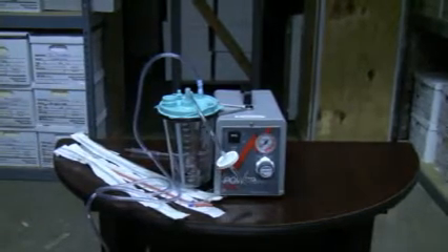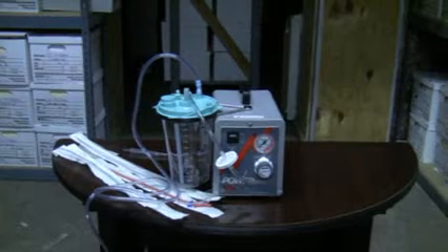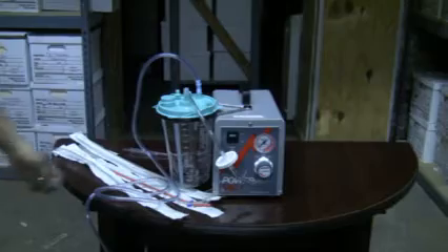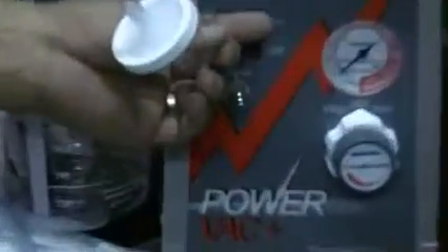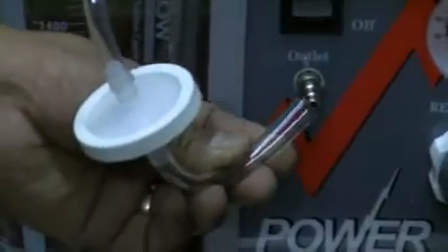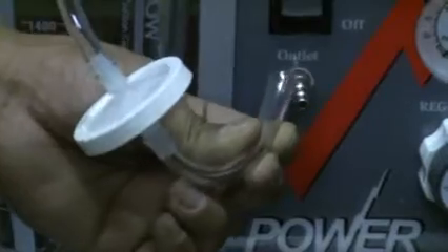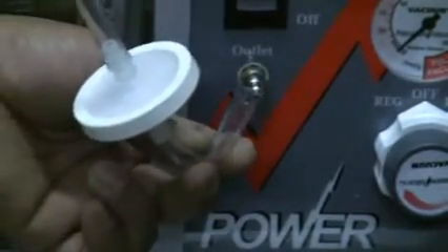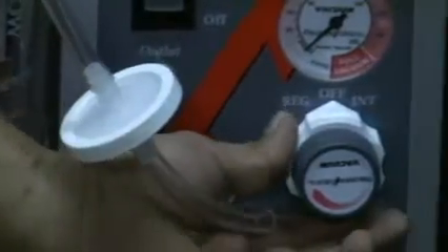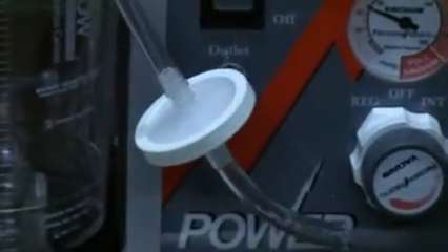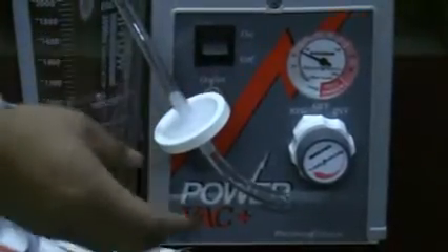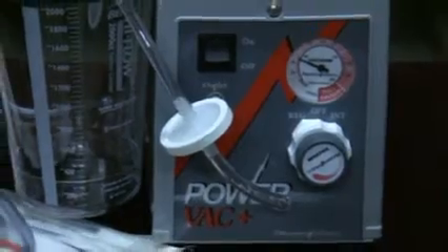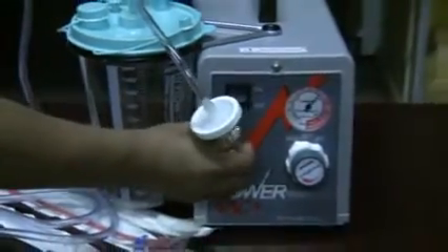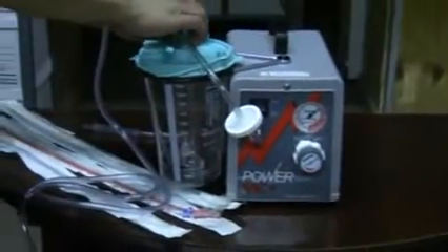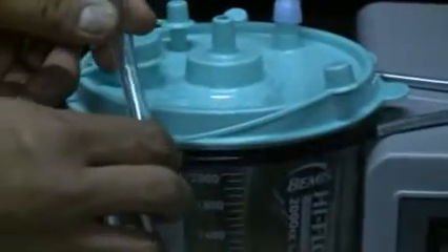intermittent suction machine pump. If you do experience no vacuum on your intermittent suction machine and there is power, you do want to check your connection here, located at the outlet. If your connection from your hydrophobic filter connected to your outlet is not connected or has been disconnected, there will be no vacuum pressure present when suctioning. So check your connection here, as well as check your connection on the top of your suction canister lid.